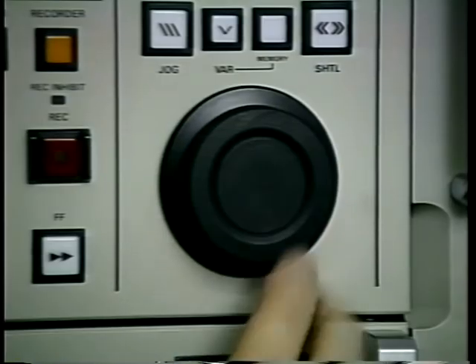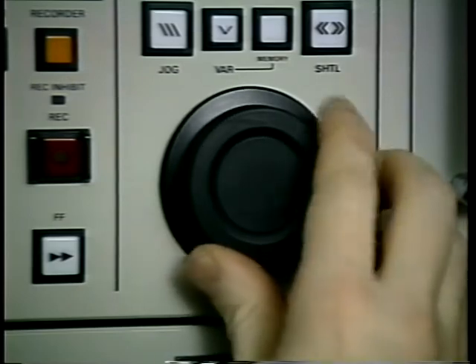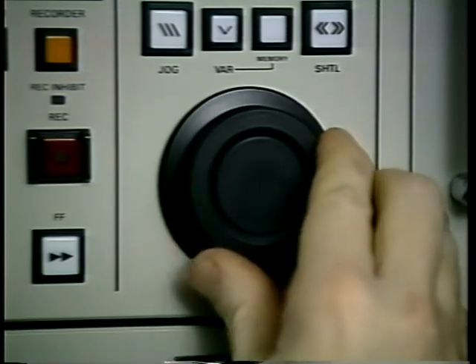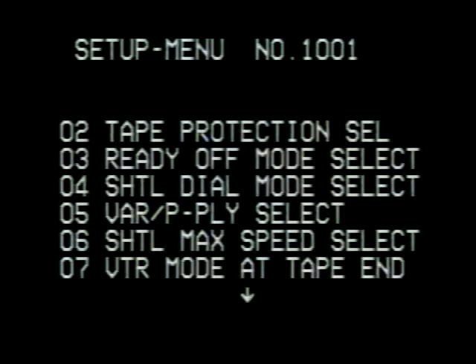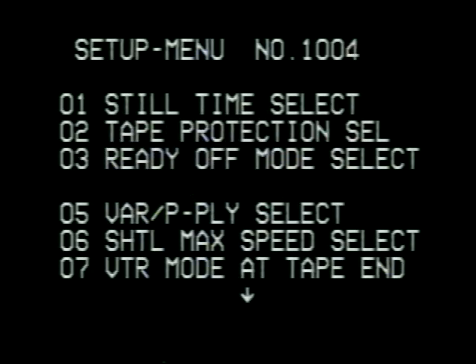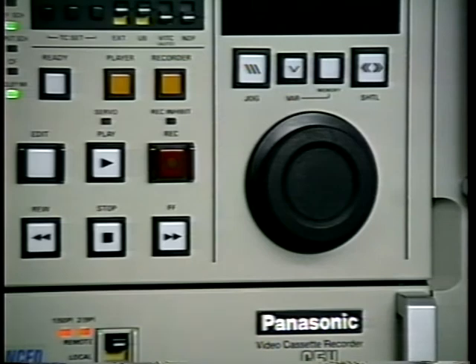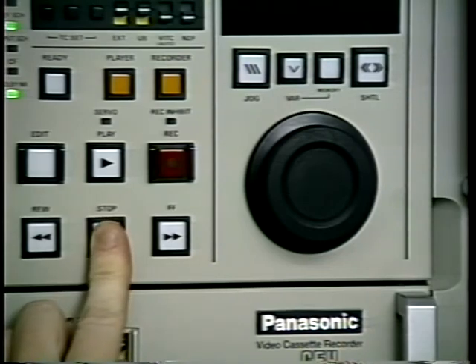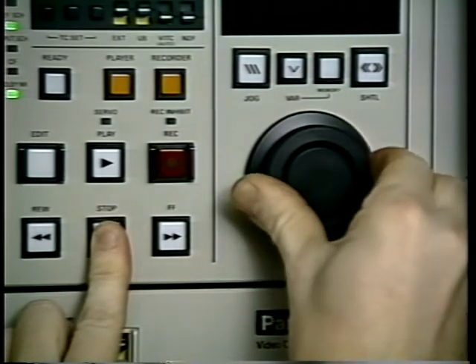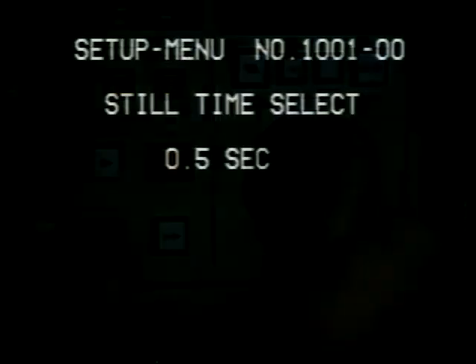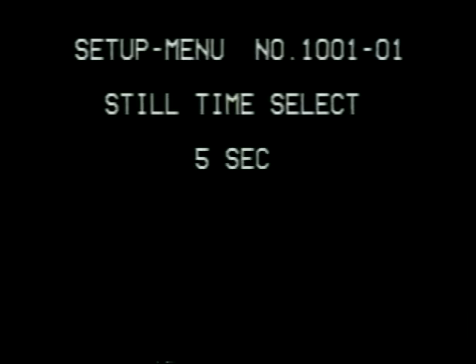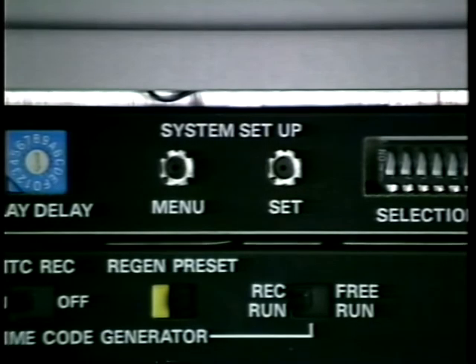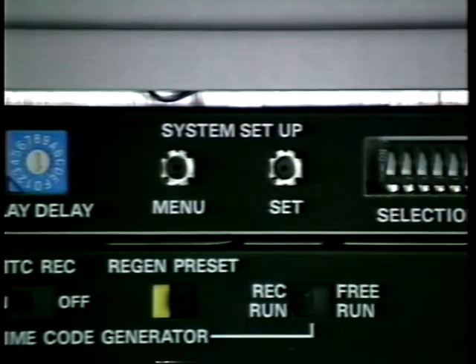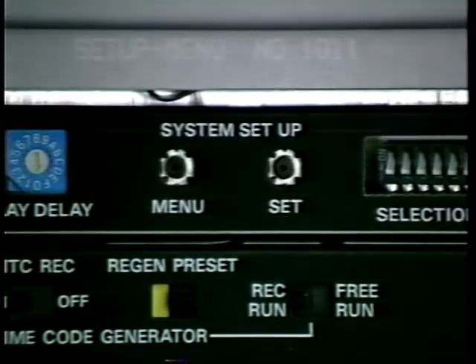To access the desired group on the main menu, turn the shuttle knob clockwise and the groups will change 1001, 1002, etc. to list your choices. To access the choices on the submenu, hold down the stop button and turn the shuttle knob to see your choices 00, 01, 02, etc. After making your selections, make sure that the set button is depressed or your selections will not be made.